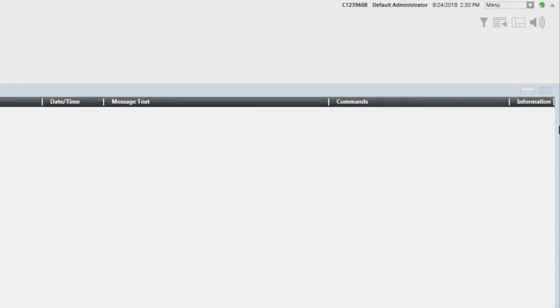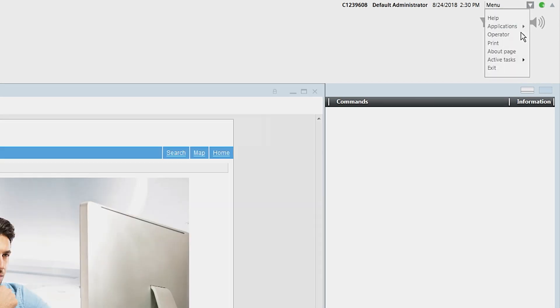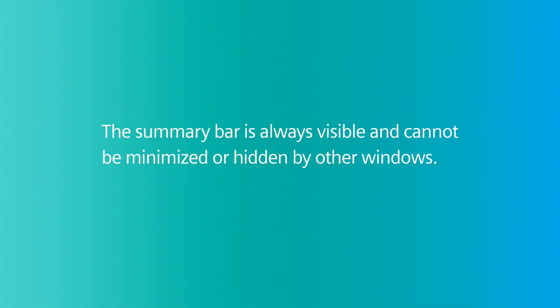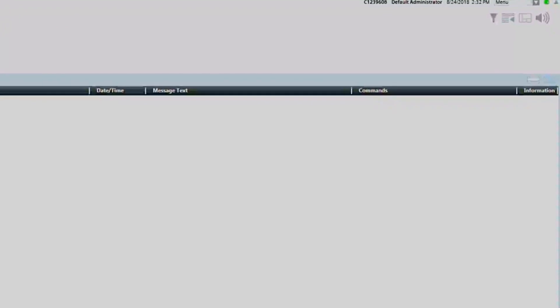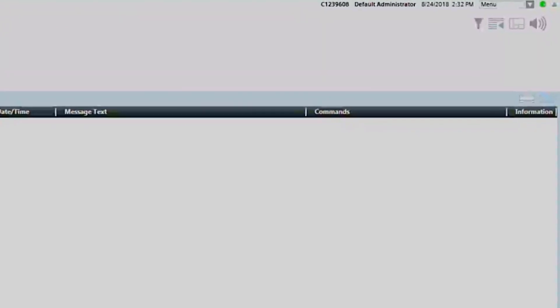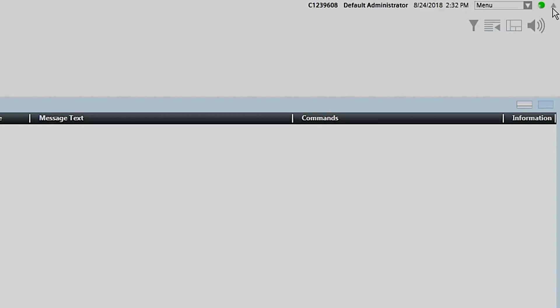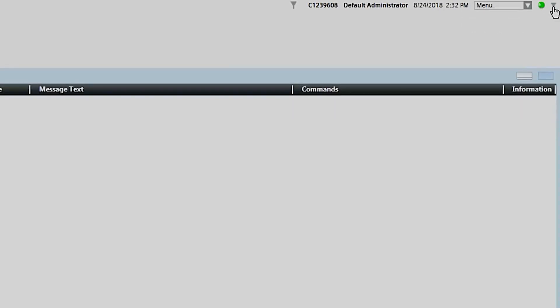The summary bar also contains information such as who is logged in, the current time and date, and a menu to access the online help tool, switch operators, and more. When all connected panels are in normal standby mode, the summary bar will indicate 0 of 0 in each event lamp, and no events will be displayed in the event detail bar. Note that the summary bar is always visible and cannot be minimized or hidden by other windows. However, it is possible to collapse the summary bar by clicking on the upward pointing triangle in the far upper right-hand corner of the summary bar.